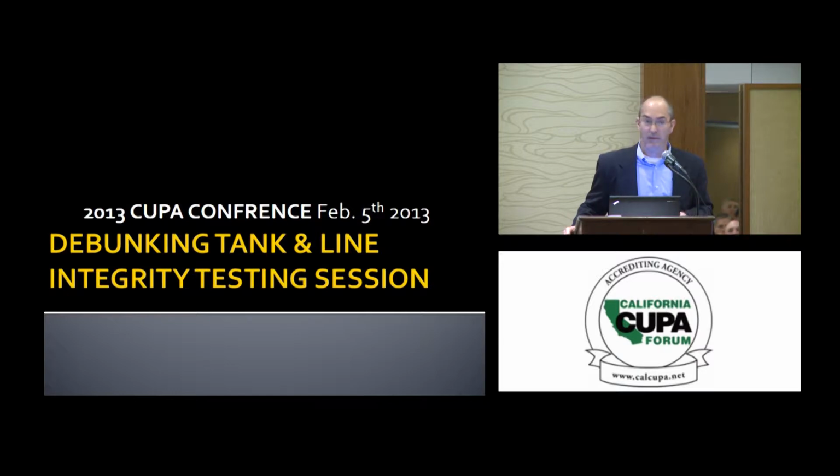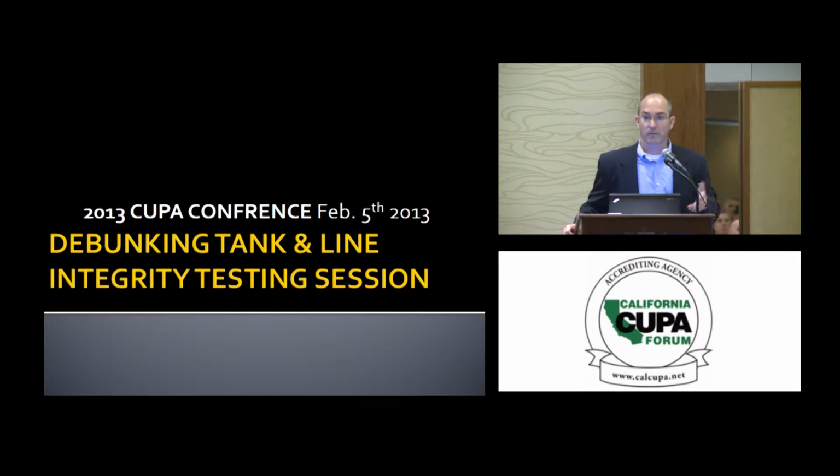I'll let Steve tell a little bit more about that with the petrotite method that his father developed. It started to accommodate a temperature measurement, and a more accurate measurement of the level to try to get an actual calculated, quantifiable leak rate. There were still some limitations of that method as well, including one that my former company, NDE, had created, which was an overfill test. We had tried as well. We threw some temperature sensors down in the tank. We had a pump to circulate the fluid and try to get the temperature to stabilize a little more quickly, but it still had some of the drawbacks of possible air pockets and end deflection and deflection of the tank.